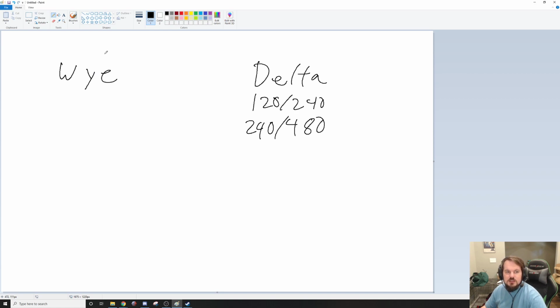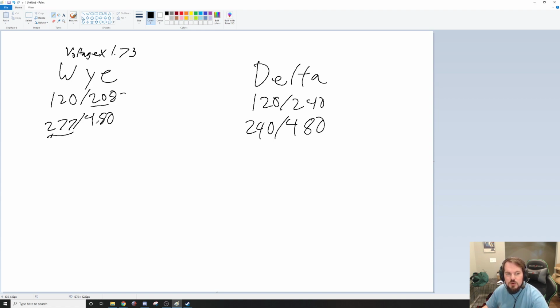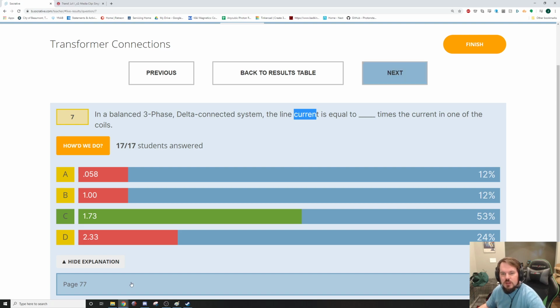Why? Since it's voltage times 1.73, instead of double the voltage, you will have 120, 208, or 277, 480. So whenever you have the weird voltages, like 208 or 277, you ask yourself why is that so weird? Why do we get the weird voltages? And it's Y. So that's how you keep it straight - Y has weird voltages, Y is voltage times 1.73.